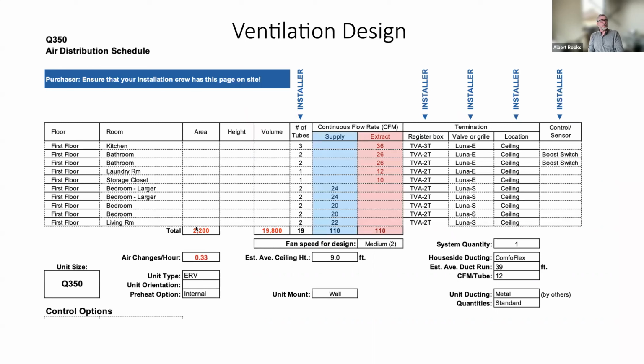And a design is simply going to be accounting for, in a balanced ventilation system, listing out all the zones: kitchen, bathroom, laundry, storage, all of those zones, and assigning an airflow. And we're going to assign supply flows in that first blue column, and this could be anybody's equipment, anybody's methodology. It's just understanding the occupancy. So blue is all about occupancy, and we're going to say a bedroom, a large bedroom.